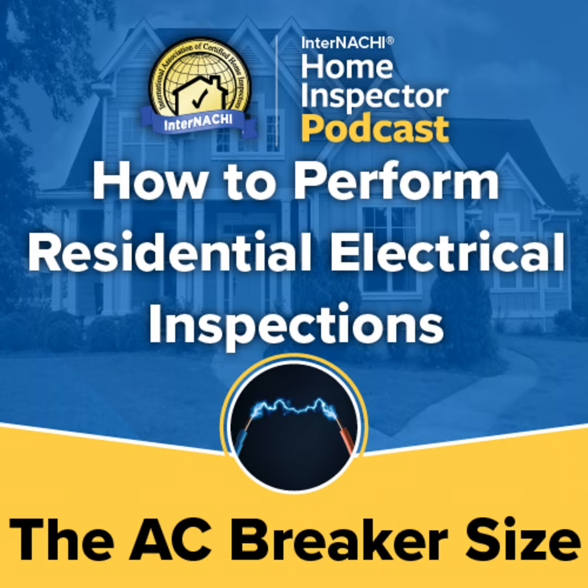The commonly known maximum overcurrent protection rules for breakers in relation to the wire size do not apply to air conditioners and heat pumps. For example, if a home inspector observes a 50 amp AC breaker on an 8-gauge wire, that may not be a defect. It might be okay and likely not a defect, even though the breaker will be sized larger than what the inspector thinks is permitted.